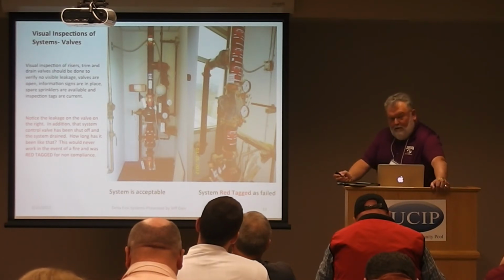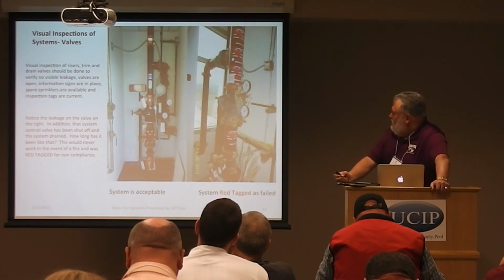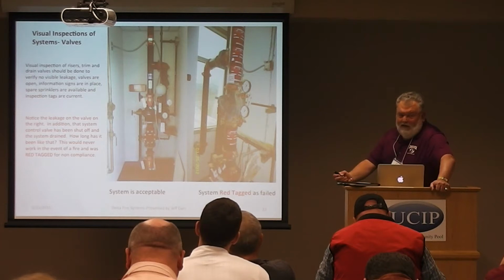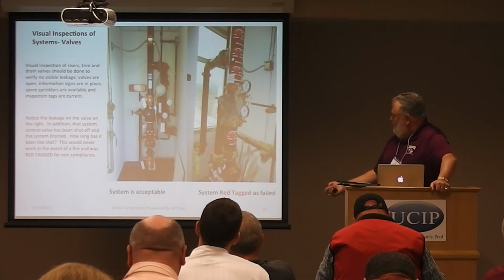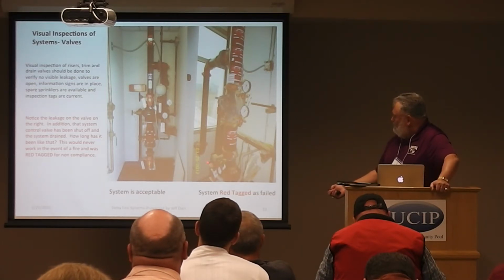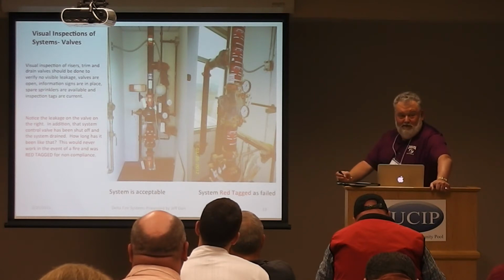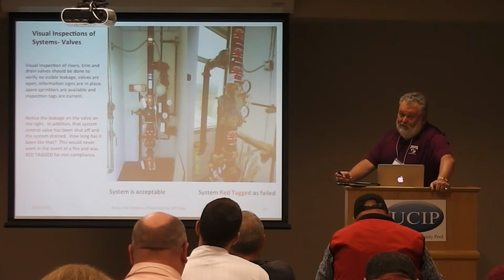Here's a side-by-side comparison. Two wet risers right here. You can see the one on the left. We can see visually from the outside it's clean, the valves are open, the gauges are up. The one on the right, you can see has been leaking externally for quite some time. You can also see down here that valve is shut off, and both gauges are reading 0. Don't know how long that system was like that when we showed up to do an inspection on it, but obviously there was a problem.